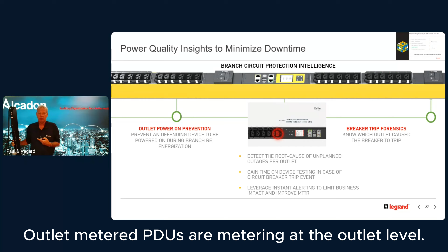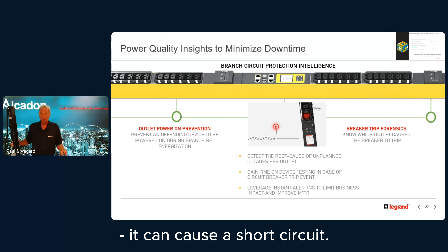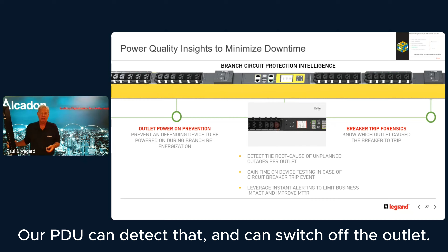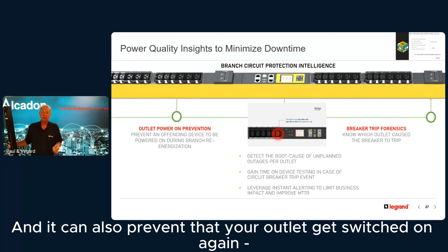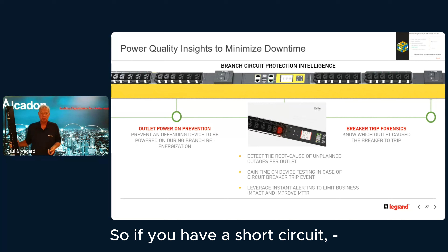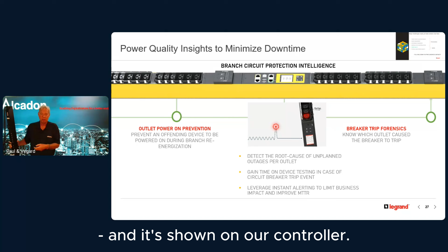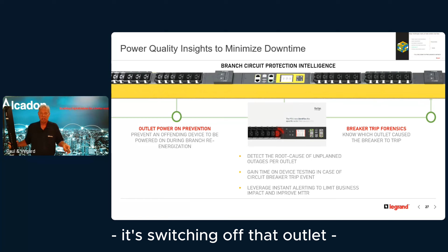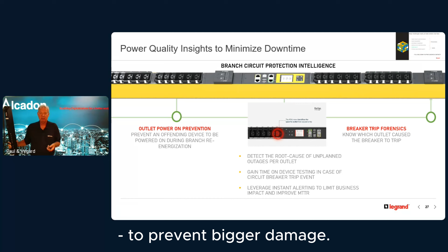We can also monitor short circuits. Outlet-metered PDUs meter at the outlet level. If a power supply of a server fails, it can cause a short circuit. Our PDU can detect that and switch off the outlet, and it can also prevent the outlet from being switched on again before the issue has been solved. So if you have a short circuit, it is detected and shown on the GUI, on our controller. And with an outlet-switched PDU, it switches off that outlet just to prevent bigger damage.